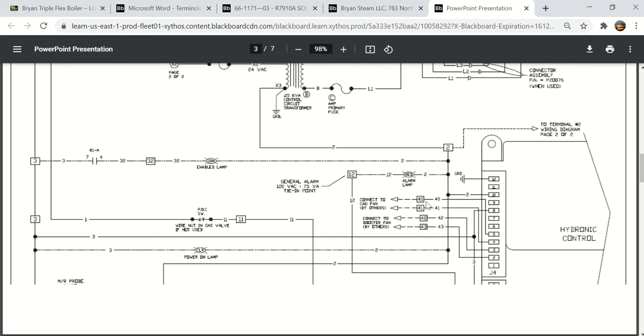So regardless, this is a contact point, and again, we'll talk about the term dry contact. There is no voltage on 40 and 41, but internally in the controller here, there is a contact that will close when it's time for the combustion air damper to open or when it's time to start the fan. And here is a connection between 42 and 43. These are boiler terminals that you can connect a booster fan. In this case, booster fan means an exhaust booster or a flue exhaust fan. And that comes down to terminals 3 and 2, and the combustion air damper was 4 and 5.